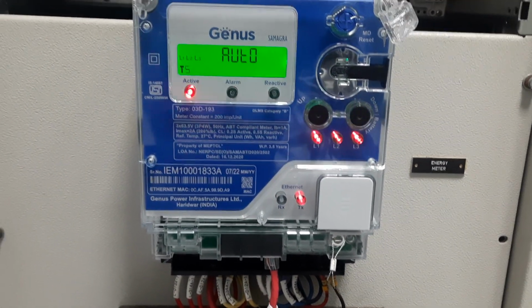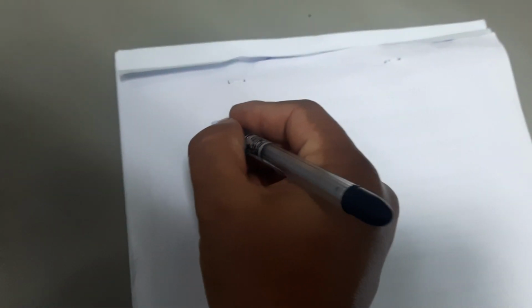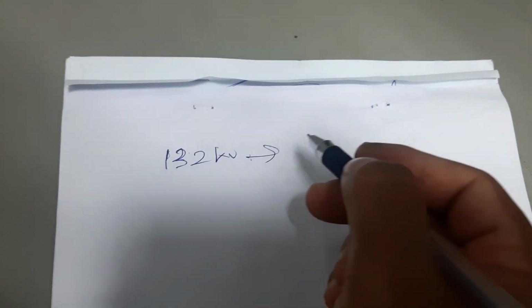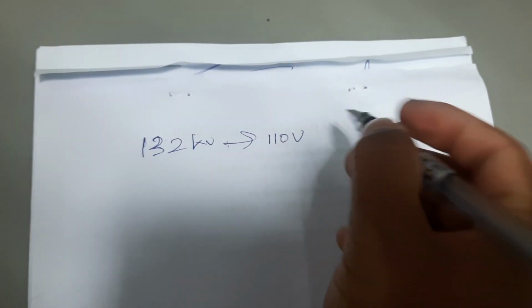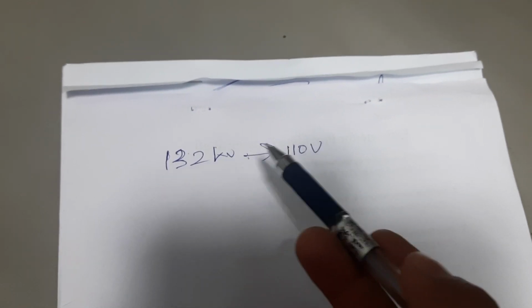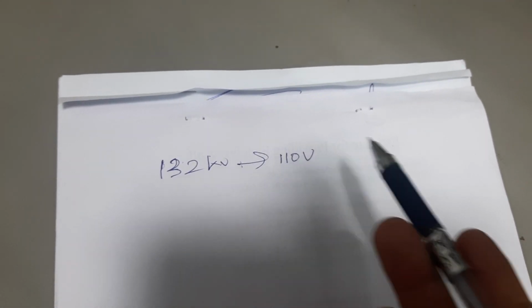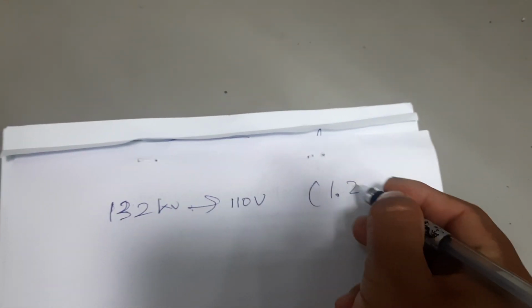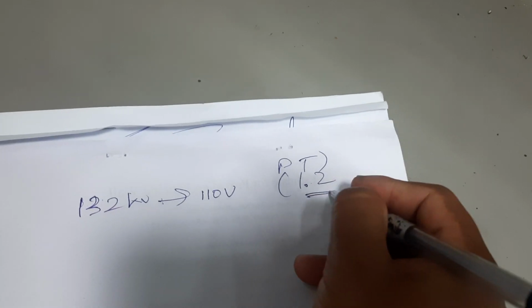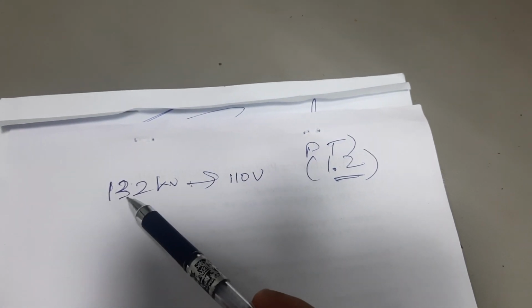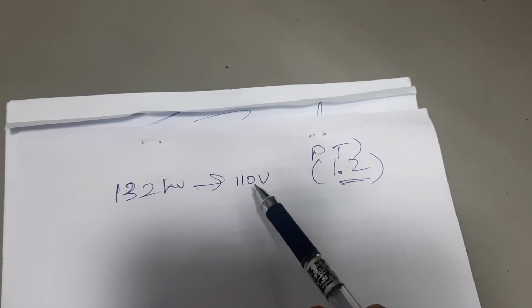Our primary voltage, if you look at the bus voltage, will be 132 kV, plus minus 5%, but let us take 132. Our respective secondary voltage will be 110 volt. So the PT ratio, CVT ratio or PT ratio, is 1.2. That means if we have 132 kV in the primary, we have 110 volt in the secondary.